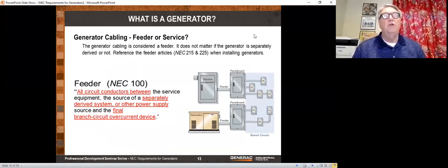Now, there are 3 types of wires, and one of them is your service entrance, one of them is feeders, and one of them is branch circuits. So feeders, and this is out of NEC 100, which is the definition section of the National Electrical Code. A feeder is all circuit conductors between the service equipment, the source of a separately derived system, or other power supply source, and the final branch overcurrent device. Now, a branch circuit is one that actually feeds the actual load. It goes to a motor, it goes to a receptacle, it goes to lighting or whatever. That's your branch circuit. They feed the loads.